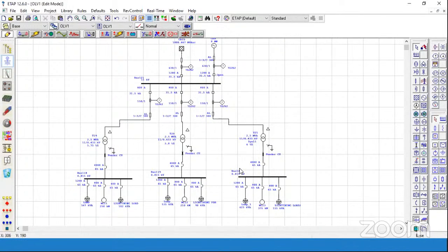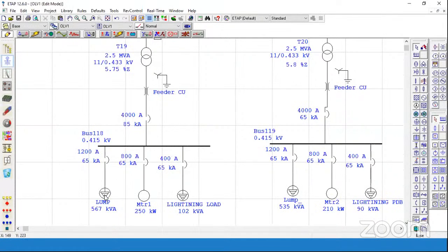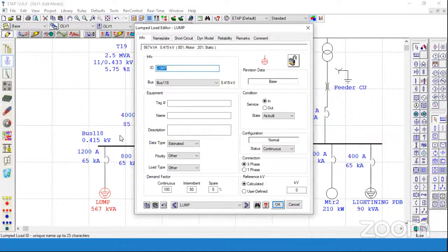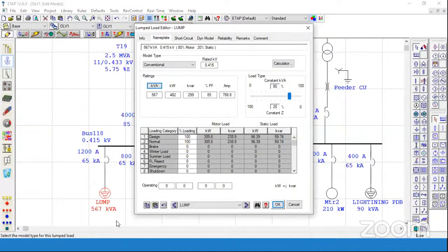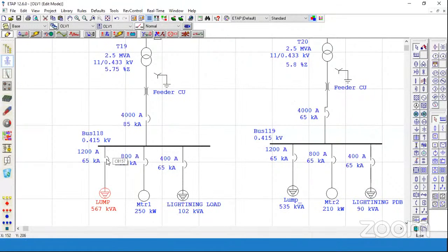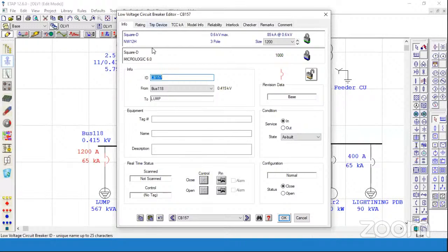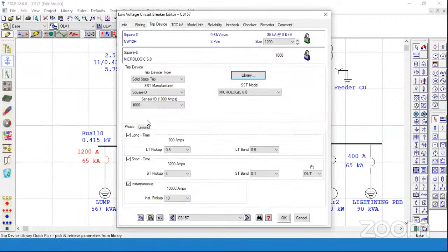Now let's go to the relay settings calculation side. In order to calculate relay settings, we need certain parameters, like what kind of load is connected to our system and what its full load ampere is. Now let's say here for the lump load, the full load ampere is 788 ampere. So we will set the overcurrent protection in such a way that if the current goes beyond its rated ampere, that is 788 ampere, then this trip unit should issue a tripping command for this particular section.